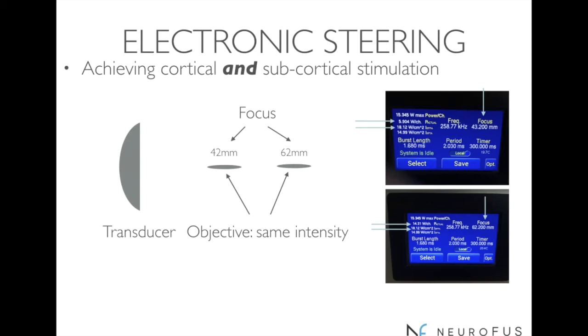In both of these examples, the ISPPA is 18.12 watts per centimeter squared. But when steering to 43.2 millimeters, the acoustic power is 5.9 watts per channel, whereas to get it to 62.2 millimeters, you need a slightly higher power of 14.3 watts per channel. The resulting ISPPA at the acoustic maximum differs between these two things.